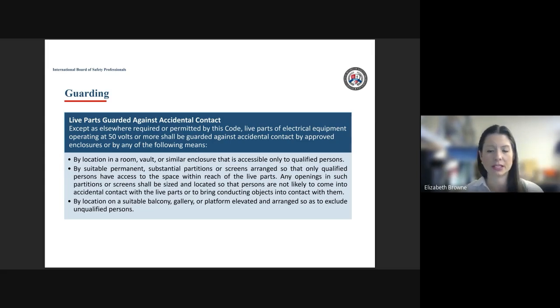And let's talk about what OSHA considers guarding in this situation. Guarding can mean by location in a room, vault, or similar enclosure that's accessible only to qualified individuals. Those rooms would need to be properly identified and labeled, also by suitable permanent substantial partitions or screens. Again, only have access for qualified persons to reach the live parts. And again, any openings into that should be guarded or located so that a person couldn't accidentally contact the live parts. And then also by location on a platform or arranged in an area like on a balcony or gallery that unqualified persons couldn't accidentally access.